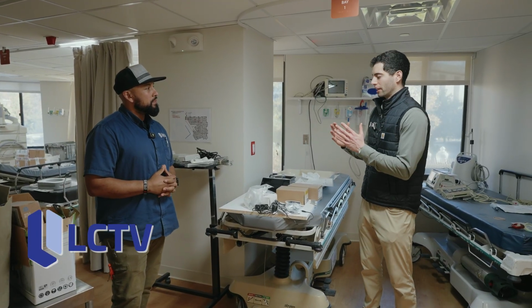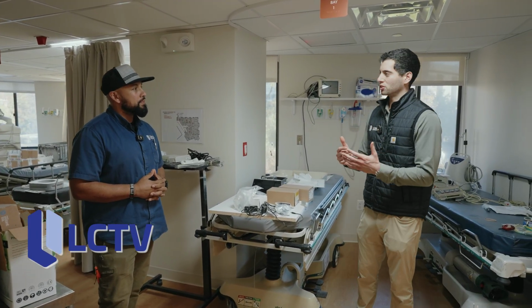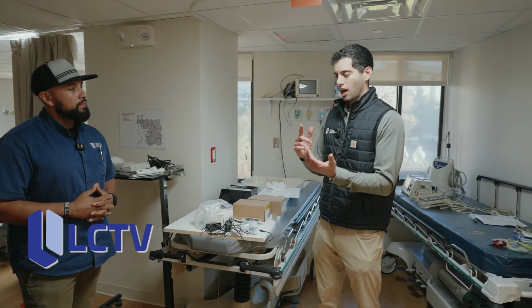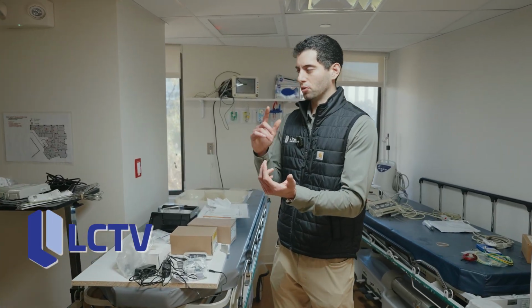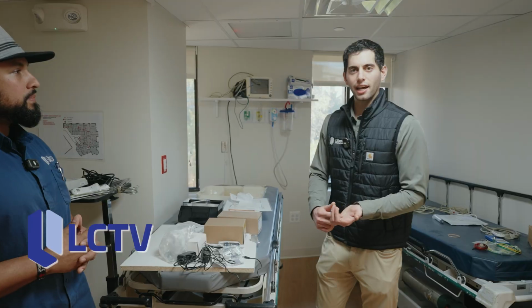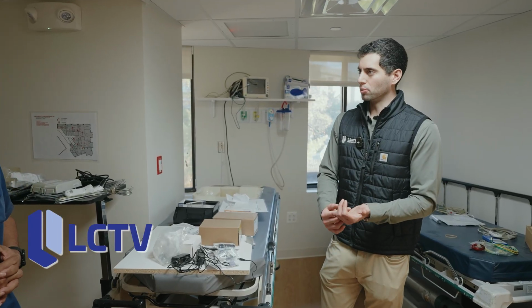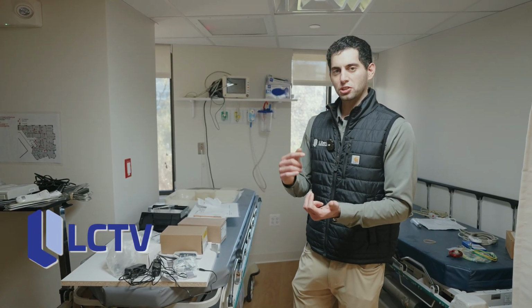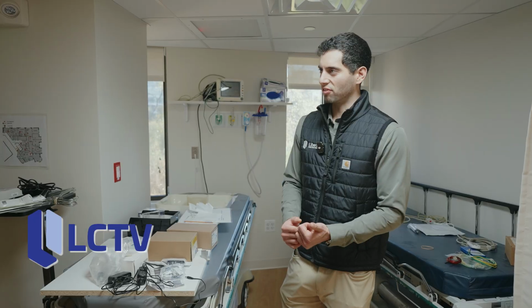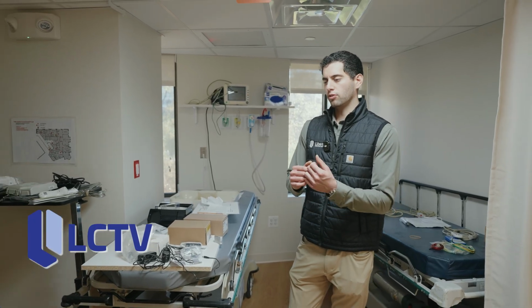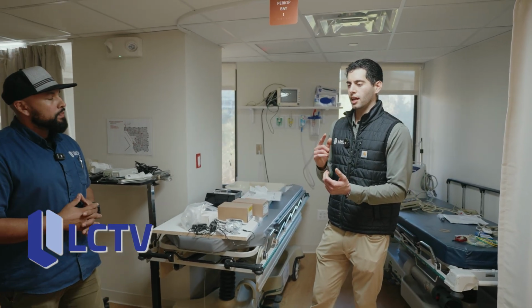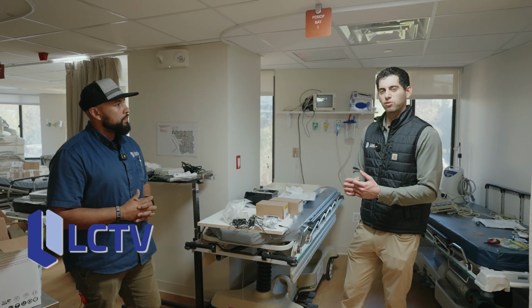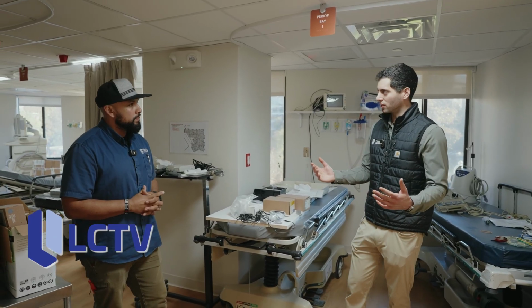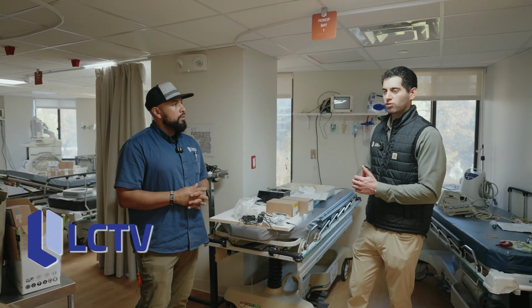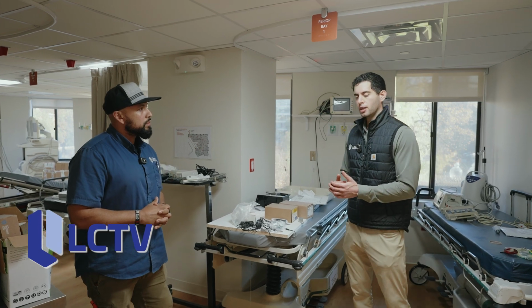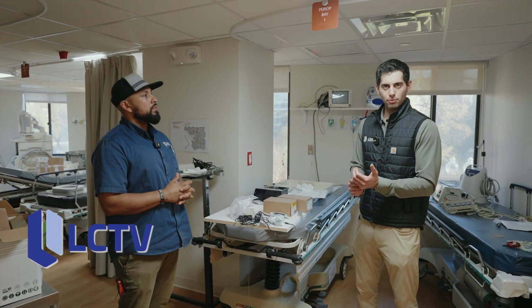Based on plans for a new ambulatory surgical center, operatories have to be at least 270 usable square feet, procedure rooms 170 square feet, and doors for operatories and procedure rooms must be a minimum of 41.5 inches, so 42 inch. We did a 4 foot wide door just to be safe, but a 3 foot door isn't going to be big enough.